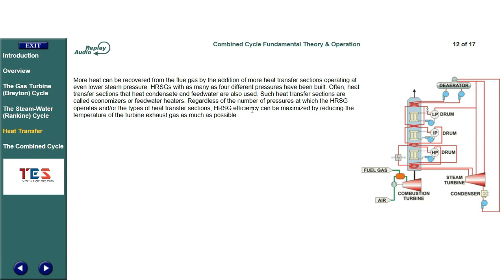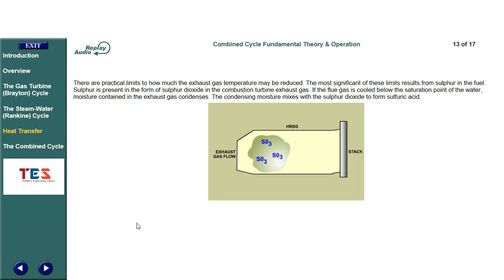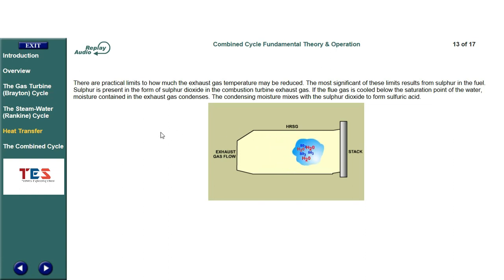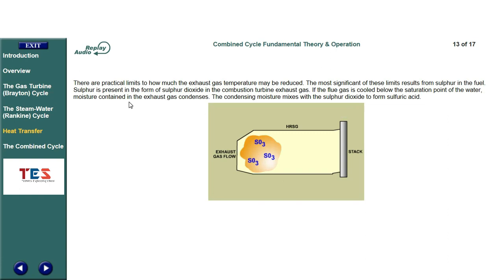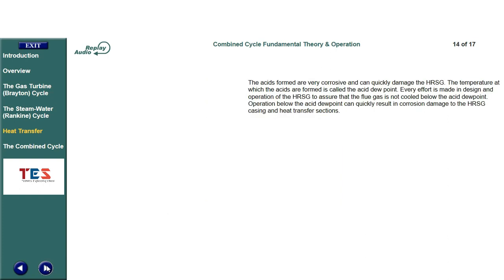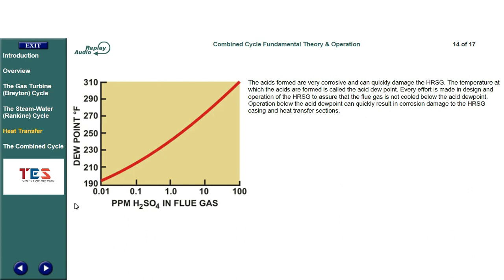Regardless of the number of pressures at which the HRSG operates or the types of heat transfer sections, HRSG efficiency can be maximized by reducing the temperature of the turbine exhaust gas as much as possible. There are practical limits to how much the exhaust gas temperature may be reduced. The most significant of these limits results from sulfur in the fuel, which is present as sulfur dioxide in the combustion turbine exhaust gas. If the flue gas is cooled below the saturation point of the water, moisture contained in the exhaust gas condenses, and the condensing moisture mixes with the sulfur dioxide to form sulfuric acid. The acids formed are very corrosive and can quickly damage the HRSG.